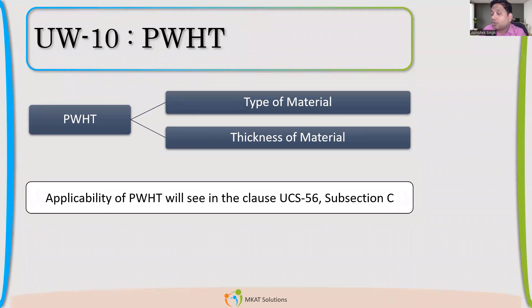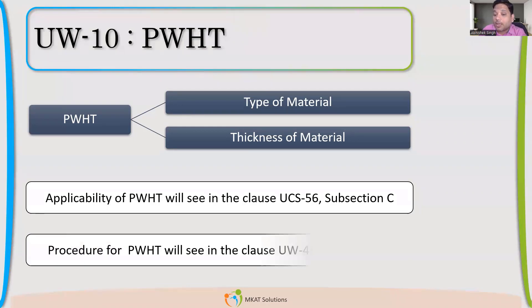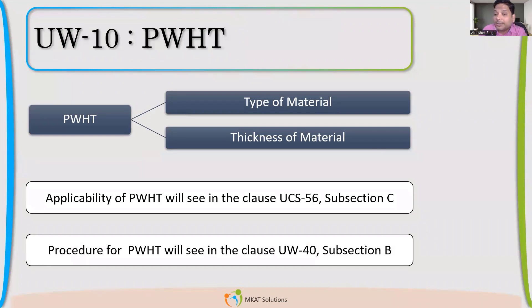So here the code only mentions that UCS-56 is the clause which we should refer. And about the procedure — like what should be my heating rate, cooling rate, and what should be the heat affected zone — all that is given in UW-40. We'll talk about that also in further chapters.